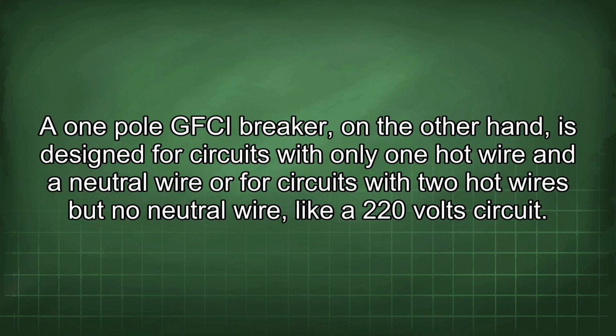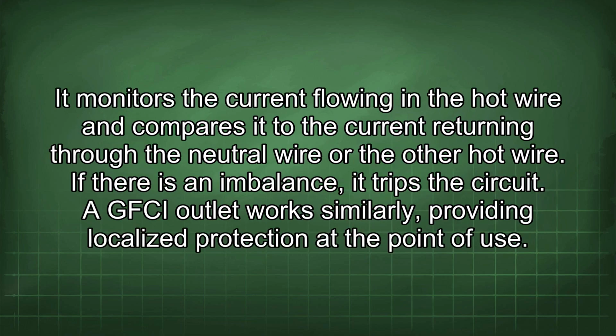A 1-pole GFCI breaker, on the other hand, is designed for circuits with only 1 hot wire and a neutral wire, or for circuits with 2 hot wires but no neutral wire, like a 220 volt circuit. It monitors the current flowing in the hot wire and compares it to the current returning through the neutral wire or the other hot wire. If there is an imbalance, it trips the circuit. A GFCI outlet works similarly, providing localized protection at the point of use.